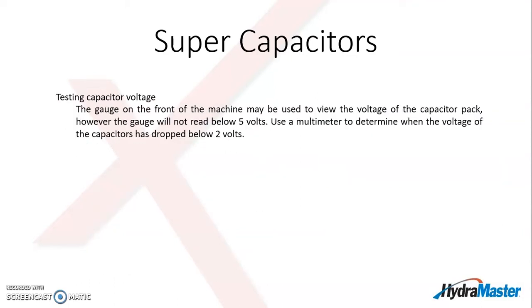You can test the voltage of the capacitor pack. You can do it with a multimeter, but you can also use the gauge that's on the front of the machine. The gauge on the front of the machine will read the voltage of the capacitor pack down to about 5 volts, and then the gauge stops reading. So at that point, you do need to use a multimeter to test the voltage on the capacitor pack and try and get it down below 2 volts before you initiate any work on the 48 volt side of the system.